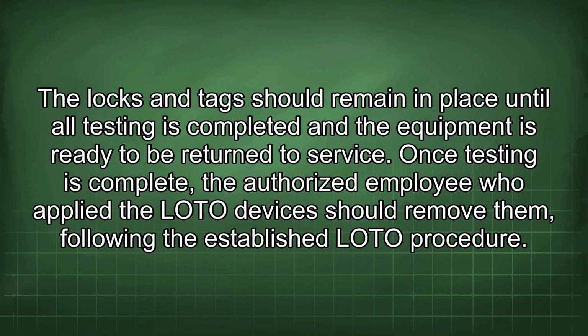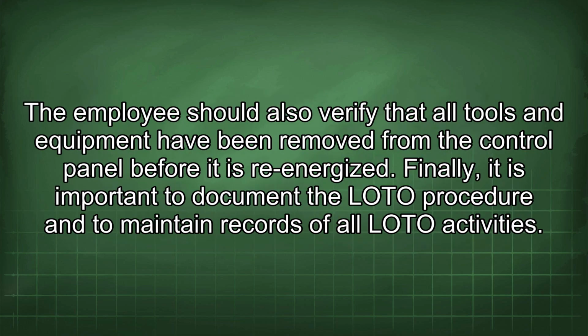The locks and tags should remain in place until all testing is completed and the equipment is ready to be returned to service. Once testing is complete, the authorized employee who applied the LOTO devices should remove them following the established LOTO procedure. The employee should also verify that all tools and equipment have been removed from the control panel before it is re-energized.